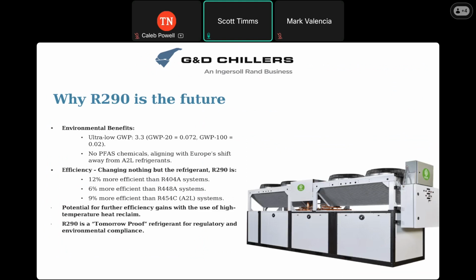Moving on to why R290 is the future: it has an ultra low GWP of 3.3. The other upside to propane is that once it's in the environment, it breaks down. Its GWP 20, meaning its global warming potential after 20 years, is less than 0.1, and after 100 years it's 0.02. So it breaks down over time. CO2 doesn't break down over time, so CO2 is going to remain at 1.